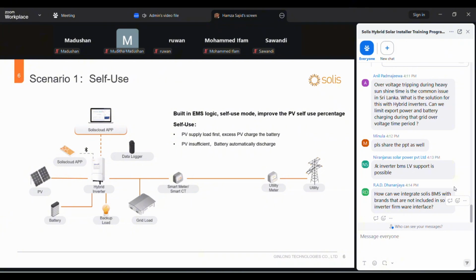Over voltage tripping during heavy sunshine time is the common issue in Sri Lanka. Okay. What is the solution for this with the hybrid inverter? Can we limit export power and the battery charging during the grid over voltage time period? Yes, you can do this.